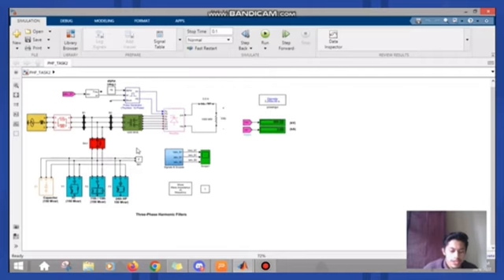Next, in this equivalent circuit, there are also three types of filter that connect with the breaker in this circuit, which is the C-type filter, using 150 megavar. The next one is the tuned filter, also using 150 megavar. And the last one is the high pass filter, also using 150 megavar. These filters will help to reduce the distortion in the equivalent circuit. After we run the equivalent circuit, we can check the output waveform from the circuit by clicking the scope here.